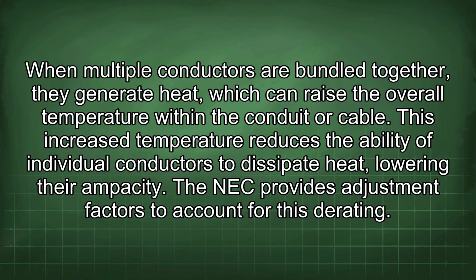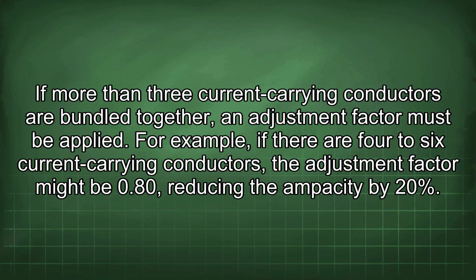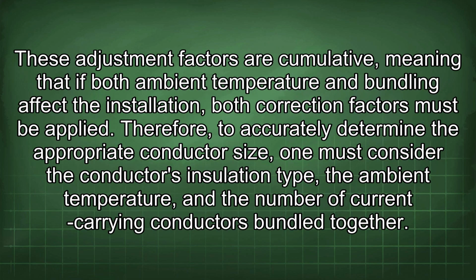Thirdly, the number of current-carrying conductors bundled together in a conduit or cable also impacts ampacity. When multiple conductors are bundled together, they generate heat, which can raise the overall temperature within the conduit or cable. This increased temperature reduces the ability of individual conductors to dissipate heat, lowering their ampacity. The NEC provides adjustment factors to account for this derating. If more than 3 current-carrying conductors are bundled together, an adjustment factor must be applied. For example, if there are 4 to 6 current-carrying conductors, the adjustment factor might be 0.80, reducing the ampacity by 20%. These adjustment factors are cumulative, meaning that if both ambient temperature and bundling affect the installation, both correction factors must be applied.